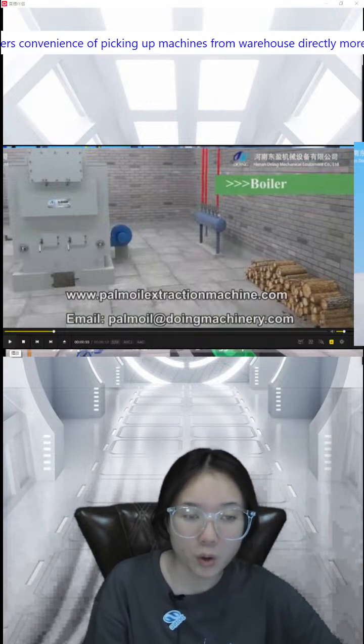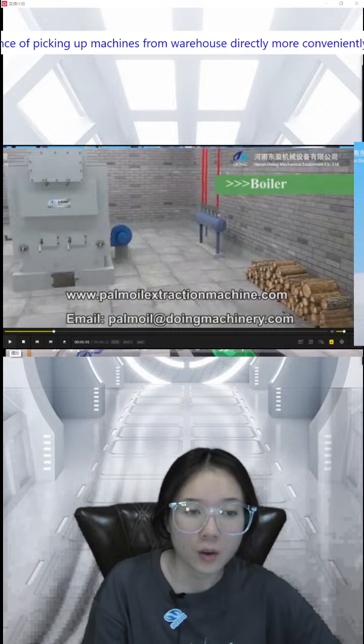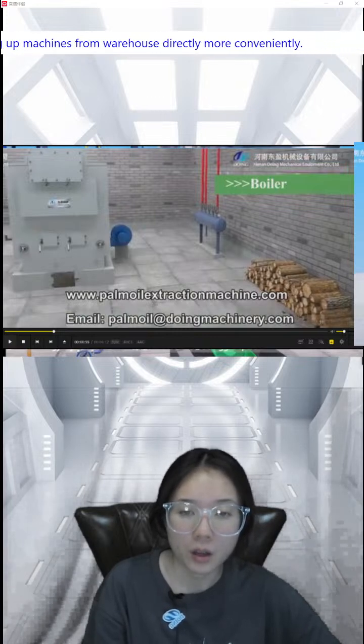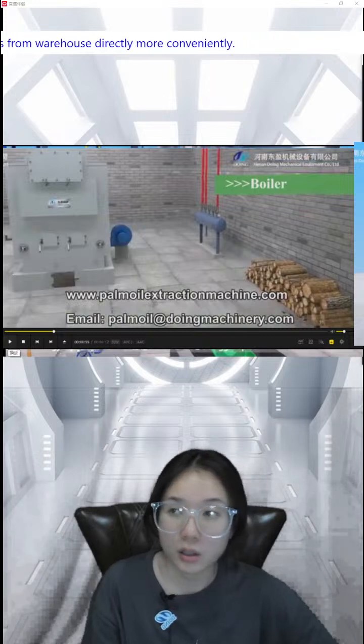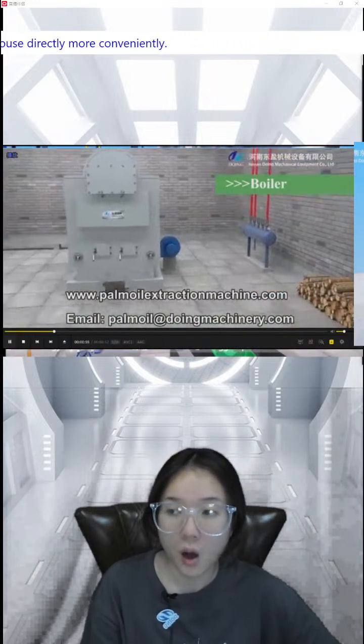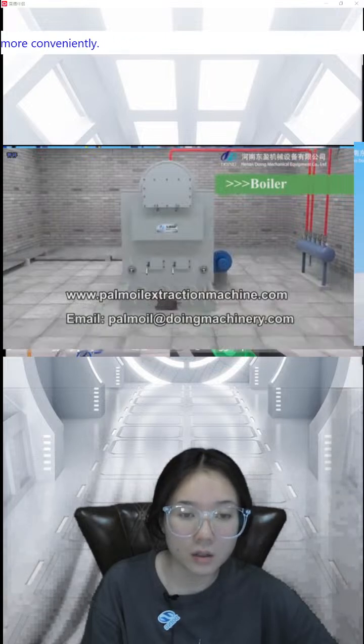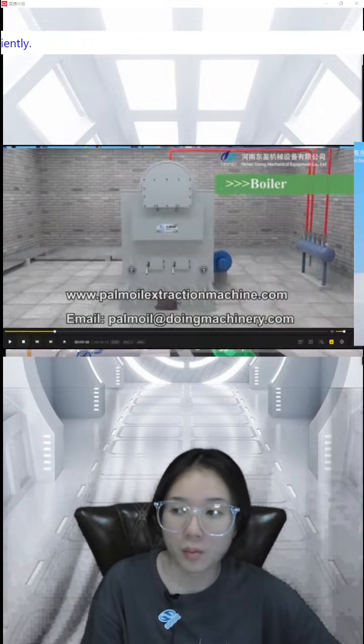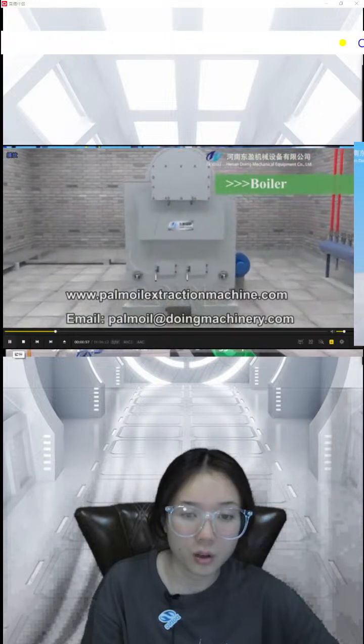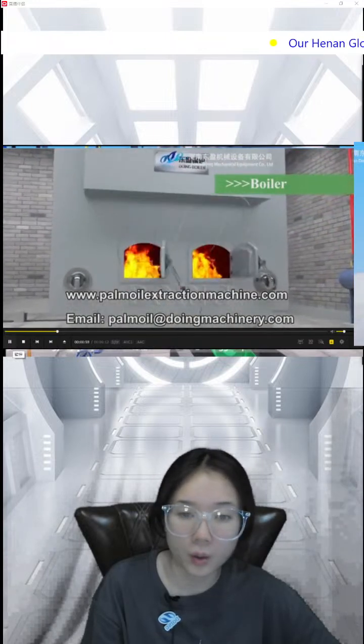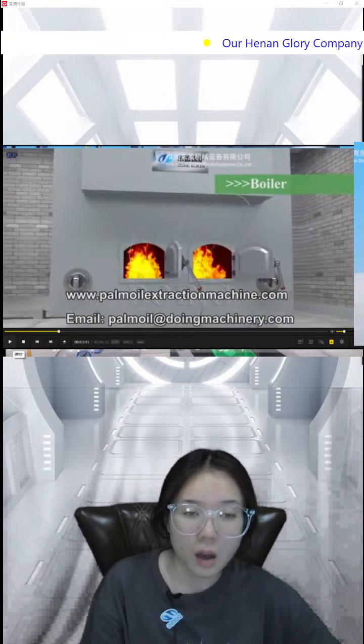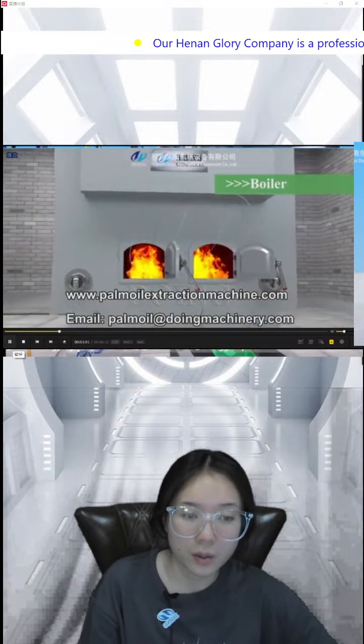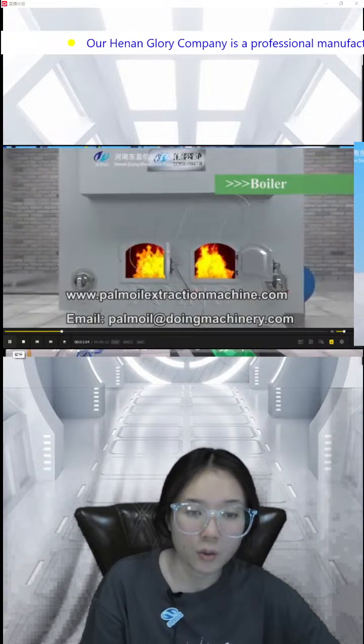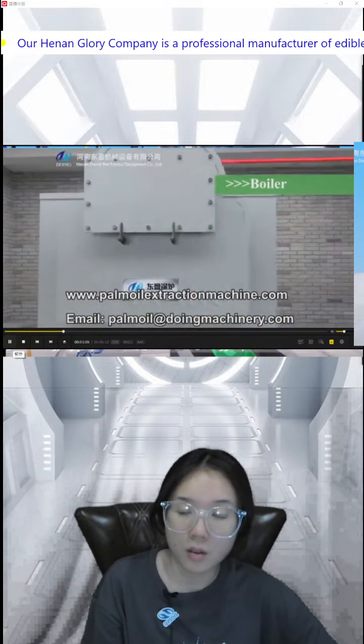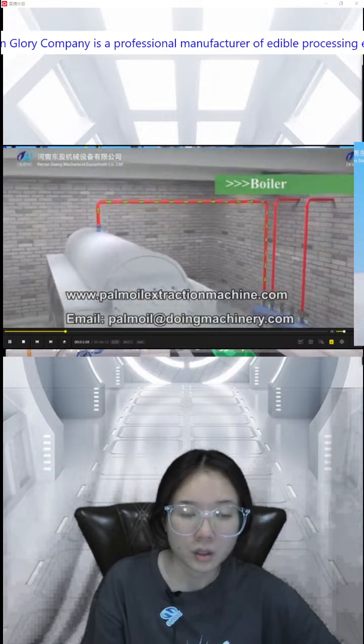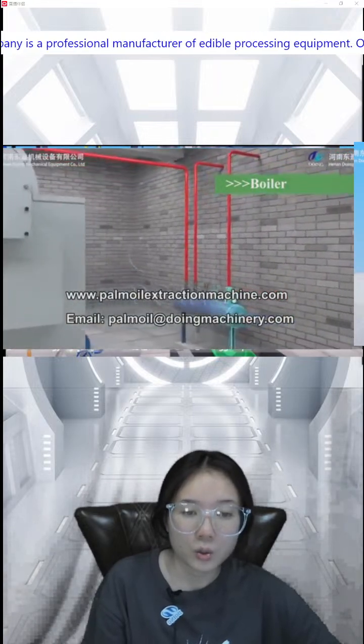And in this production line, the configuration of the cooking-type sterilizer tank needs to use our boiler. Our boiler is divided into gas boiler and biomass boiler. A biomass boiler in the palm pressing plant is more practical. The empty fruit bunches and fibers can be used as a fuel to reduce the running cost of the plant.